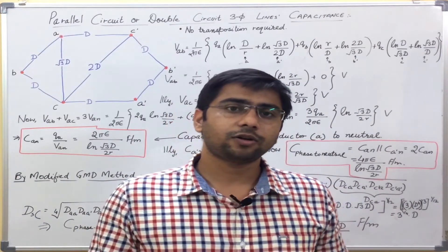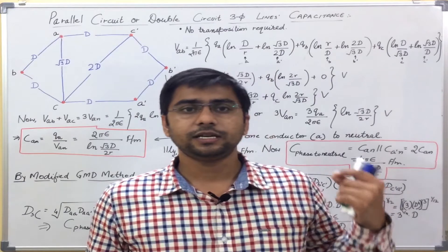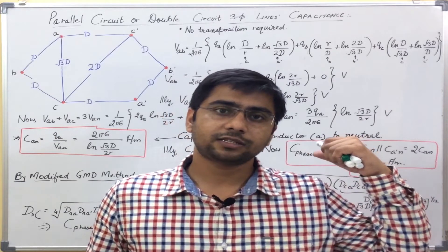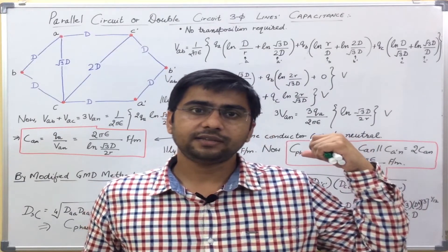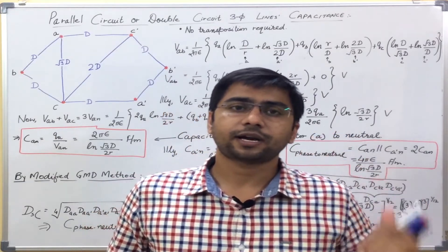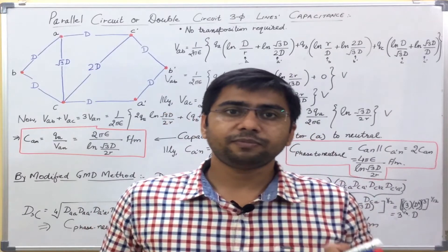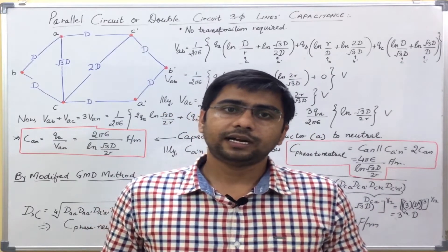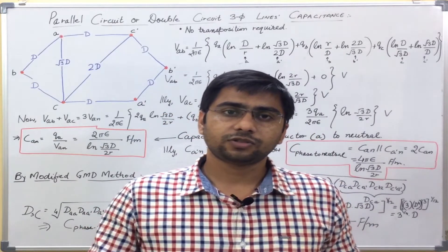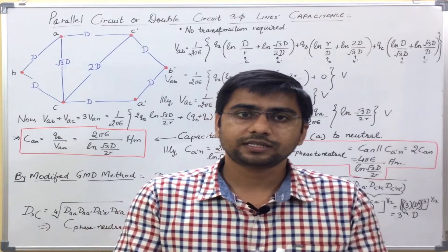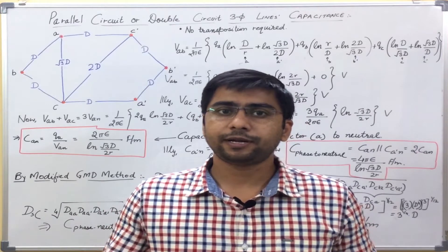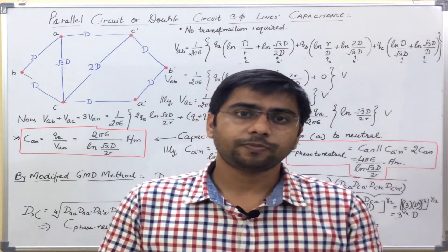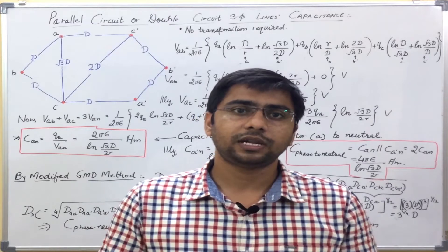There are a lot of benefits as we have already seen while deriving the inductance — we saw that we could increase the GMR, geometric mean radius of the conductor. Because of that, the inductance was reduced. This further helped in the reduction in the voltage drop along the length of the line.